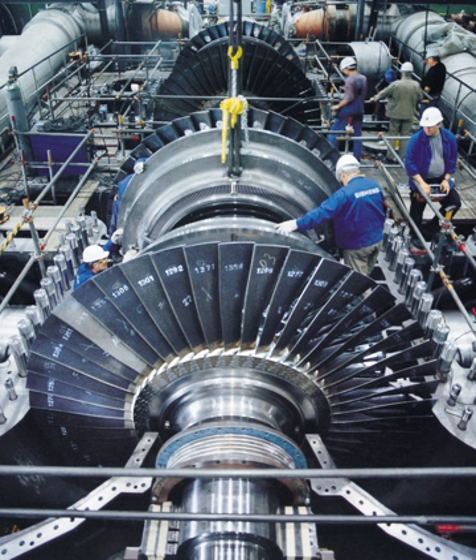These range from the obvious: how much power should the generator be able to supply? What is an acceptable length of time for starting the generator? Some generators can take hours to start. Is the availability of the power source acceptable? Some renewables are only available when the sun is shining or the wind is blowing.